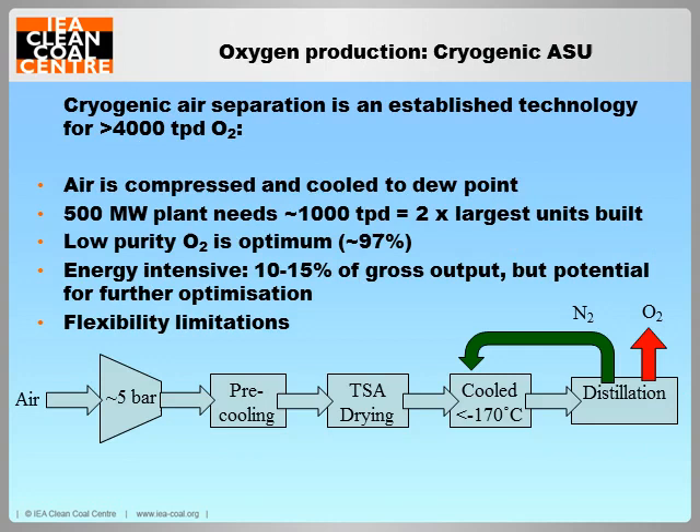Cryogenic air separation, in which air is compressed and cooled to its dew point before distillation into oxygen and nitrogen, is the only commercially available technology for the production of oxygen on the scale required by an oxy-fuel plant. With a consumption of around 2 tonnes of oxygen per net megawatt, a standard plant will actually require around two of the largest air separation units currently available. Although relatively impure oxygen can be used, the process is highly energy intensive, consuming from 10 to 15% of a plant's gross output and representing the largest parasitic load on the plant.